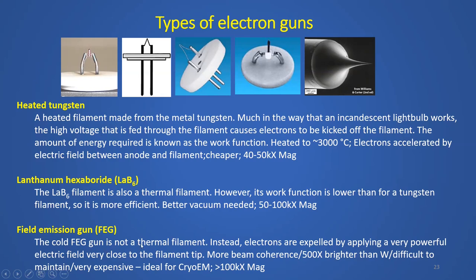And the third kind is the most sophisticated kind of electron gun that there is. This is called the field emission gun, a FEG. This is not a thermal filament. The electrons are not emitted by thermionic emission. Here, the electrons are expelled by applying a very powerful electric field very close to the tip of the filament. The result is a very coherent beam of electrons. It's around 500 times brighter than a tungsten filament. And again, it's very difficult to maintain and very expensive. Ideally for cryo-EM, you'll see that invariably you have a FEG source. Okay.